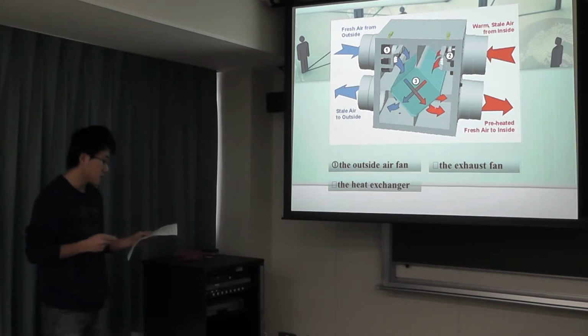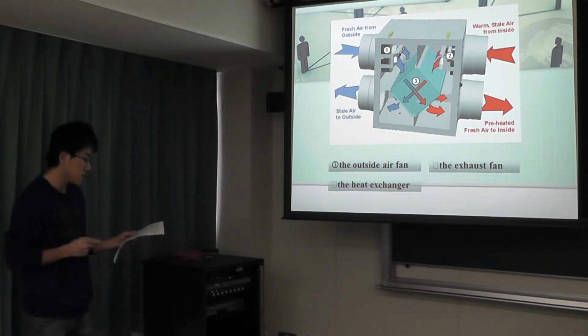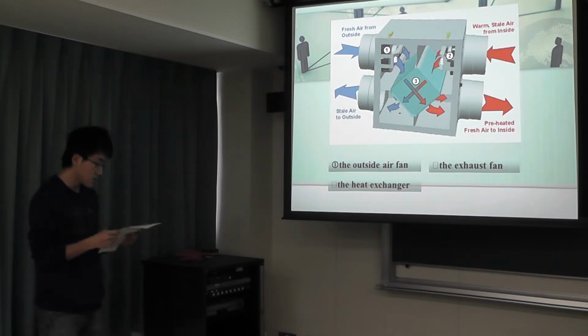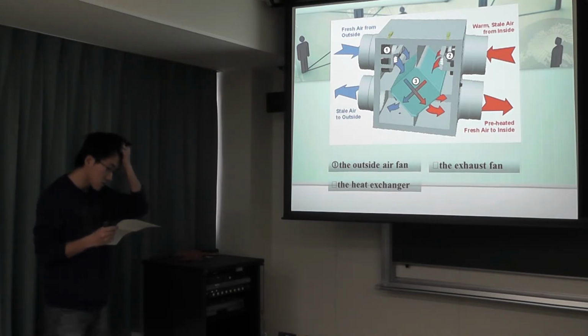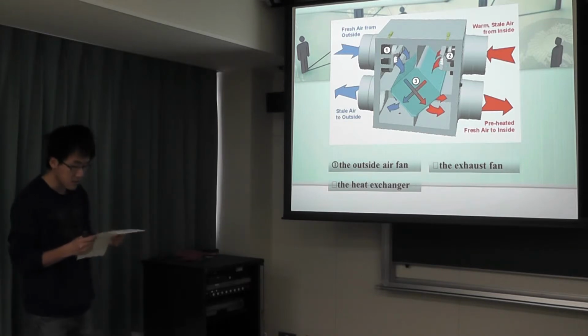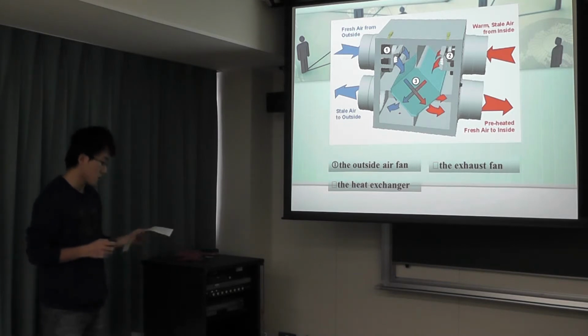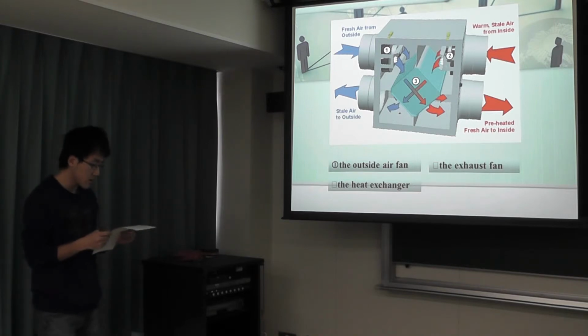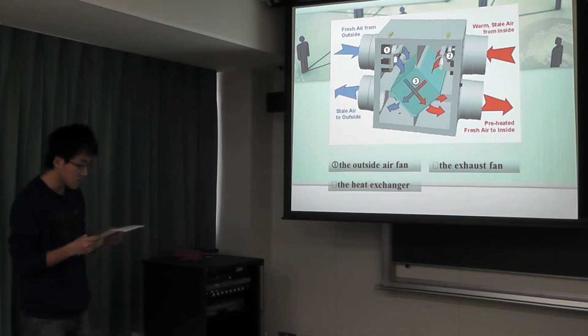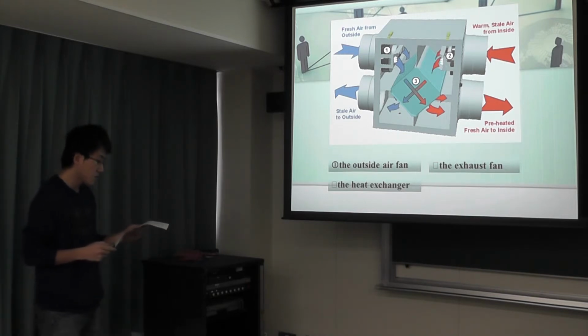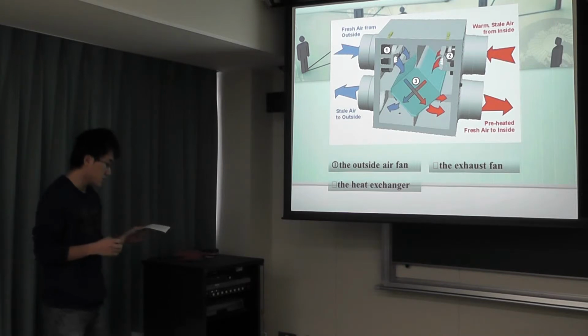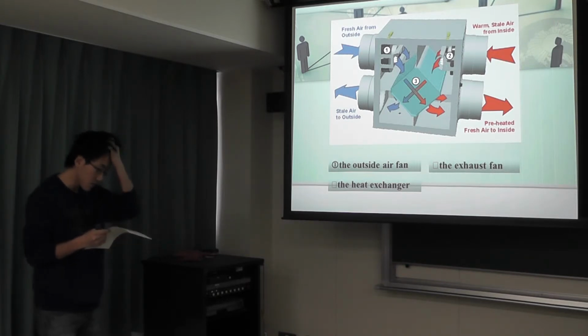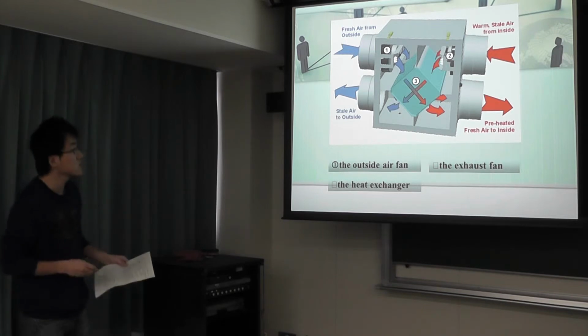This picture shows the ERV in operation during the heating season. During the cooling season, the only difference is that the cold indoor air is used to cool the hot outdoor air. The airflow remains the same, so there are no complicated mechanical systems to switch over or think about. In fact, the only thing that needs regular maintenance is the filter.